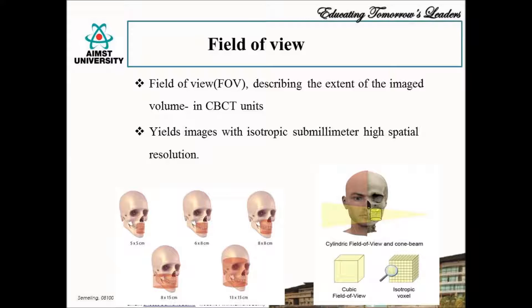An important feature of these CBCT units is the field of view, describing the extent of the image volume. This renders an in-office CBCT suitable for implant purposes, where it has the ability to control field of views, choose resolution, focus the scan only on the area of interest, and capture details according to the patient situation.